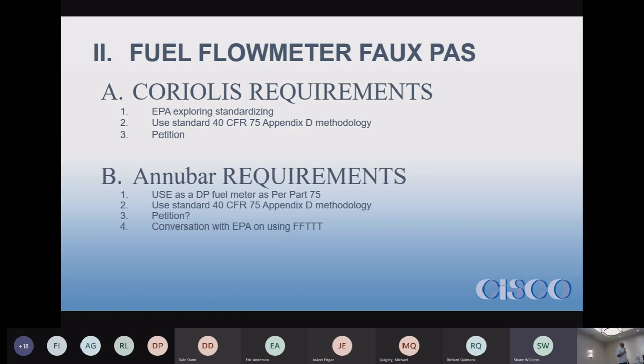This is one Melissa and I came across. Sometimes you come across new meters, and simply because you have a Part 75 site, you may conclude, I have a fuel flow meter, I can use it because I'm Part 75. Well, the Annubar meter you can use for Part 75 is the differential pressure meter, but you have to use it as a differential pressure meter according to the requirements of Part 75. Or you can use the standard Part 75 methodology, where you do an inline comparison or send it out to compare flows. The issue is what we ran into at the facility.